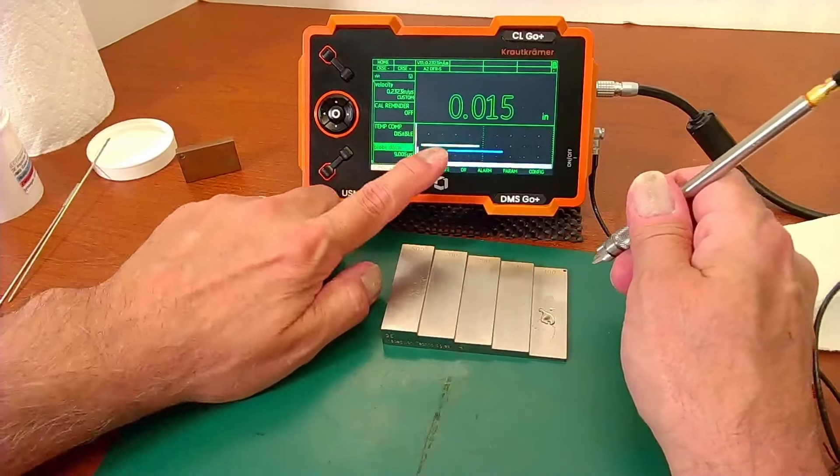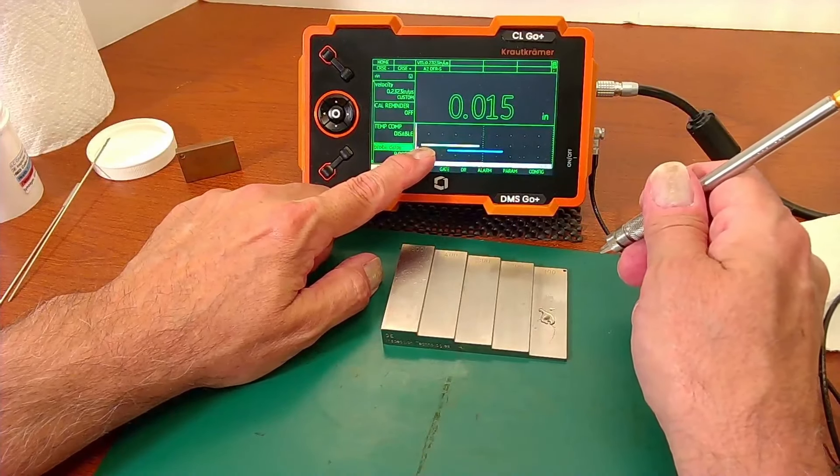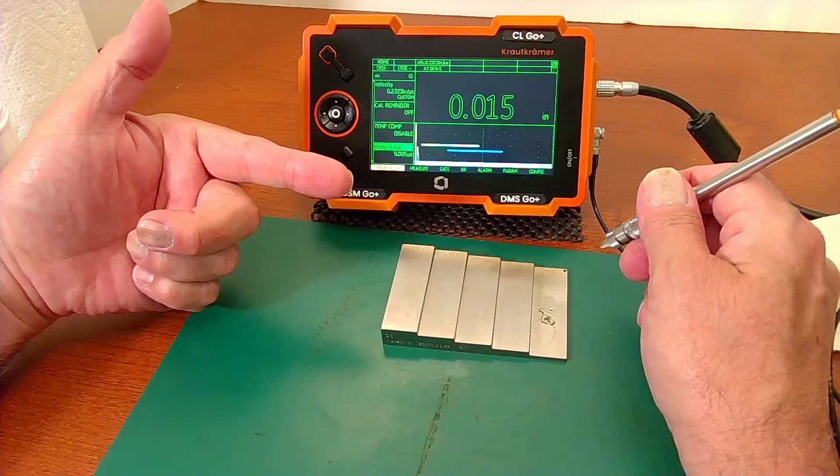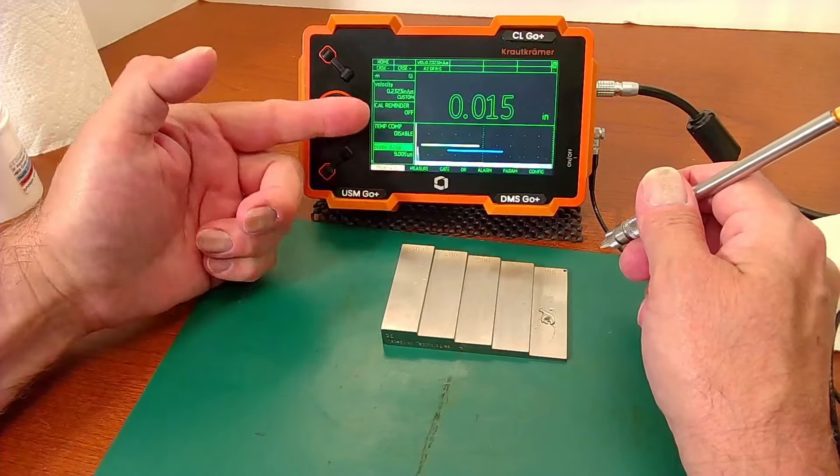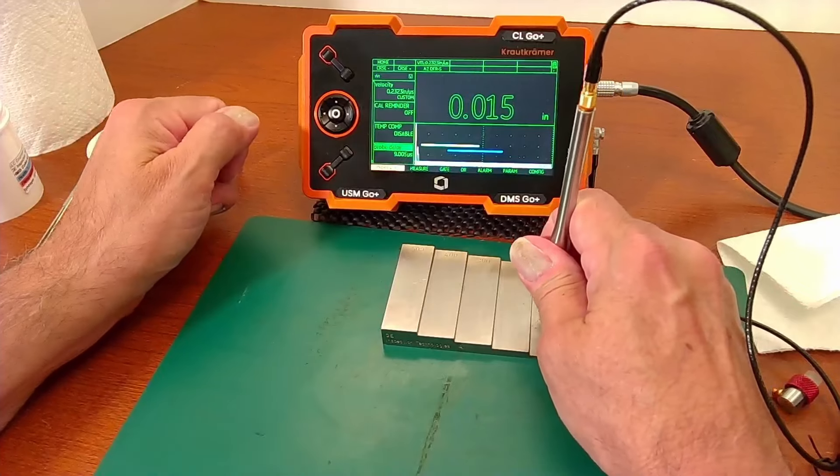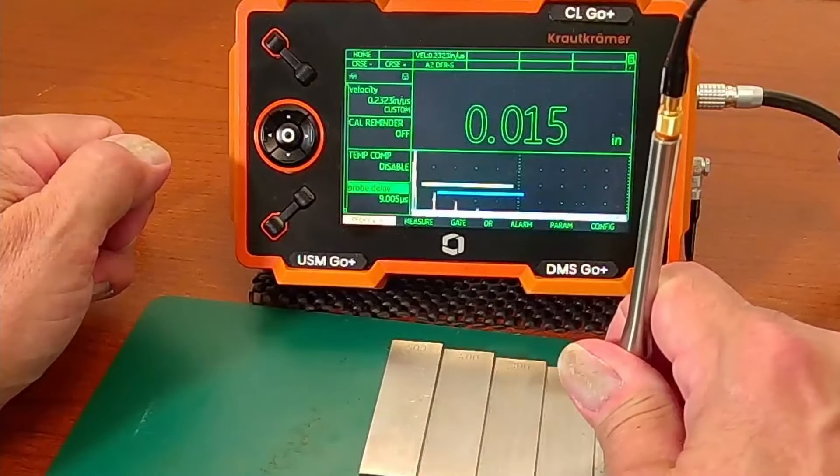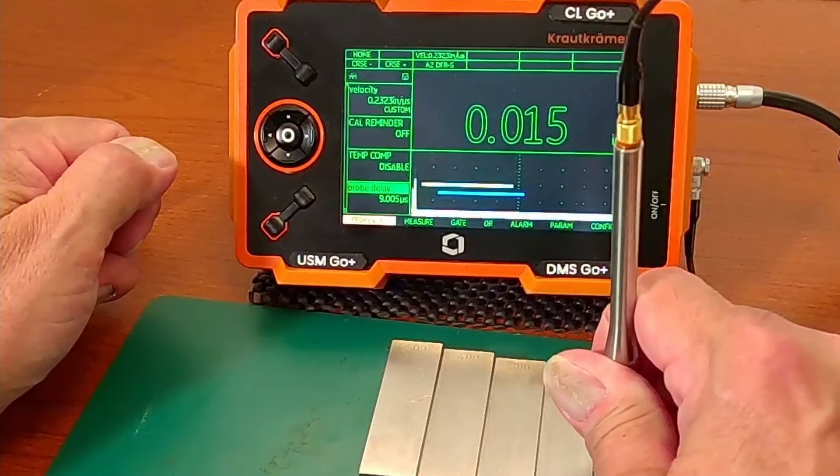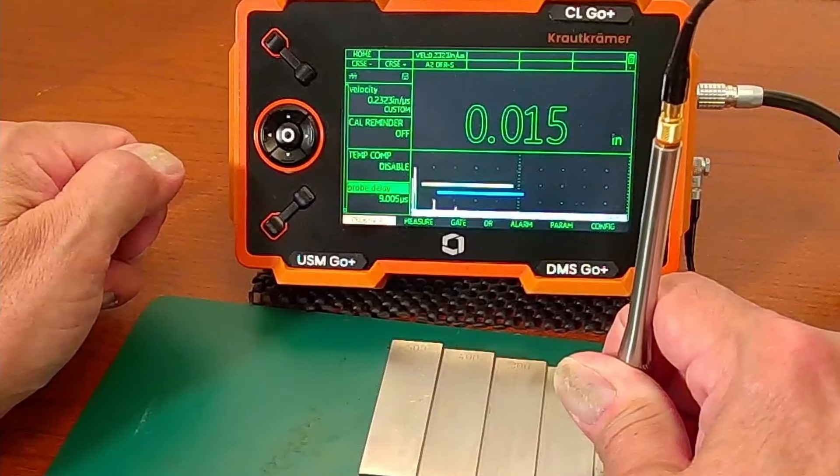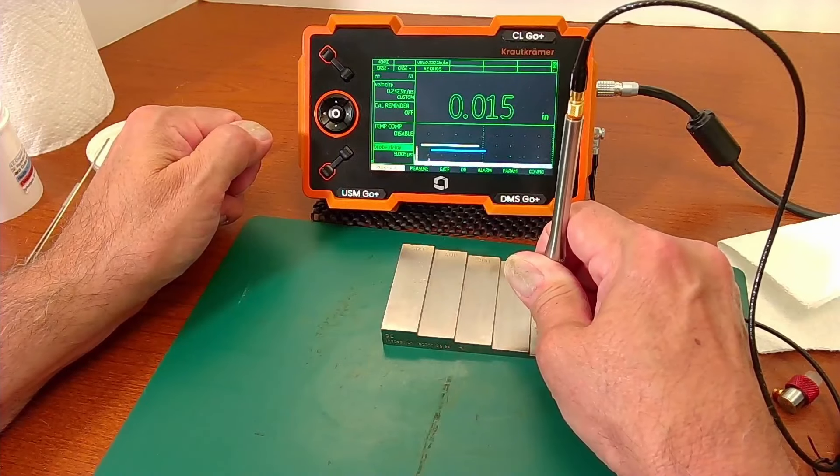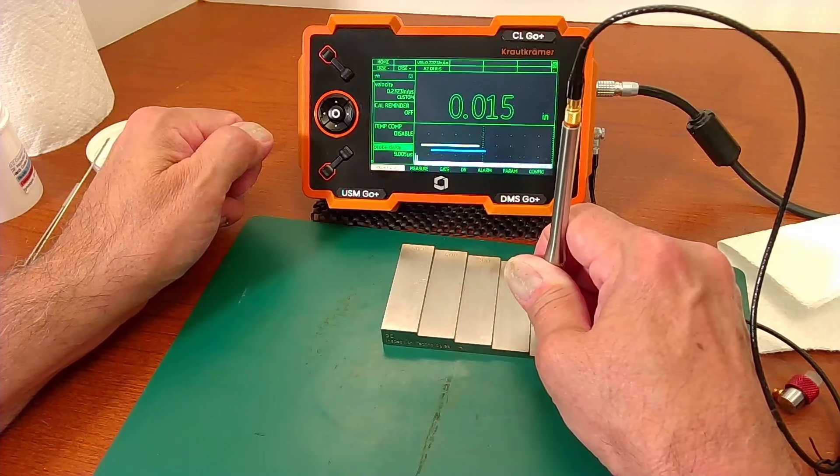One of the real advantages to using the DMS Go is you have a pretty rapid update rate. You're typically firing 16 shots per second in the DMS Go, and you have a nice live color A-scan. When I put the probe down, I can see if I'm presenting the probe nice and square to the part. I can peak up the echoes and I can tell whether I'm set up or not. You notice that even when I get perfectly square and my signal is peaked up, I still don't have quite enough amplitude to trigger the gates.